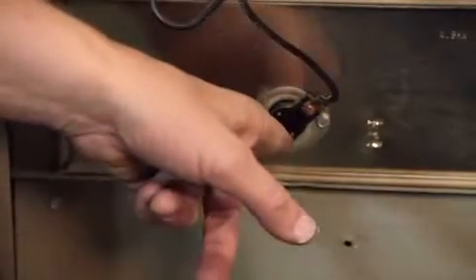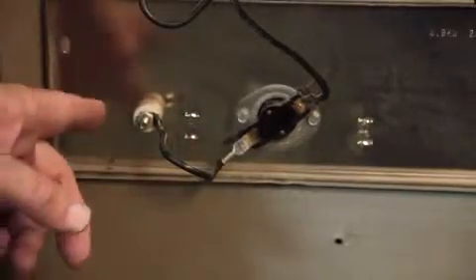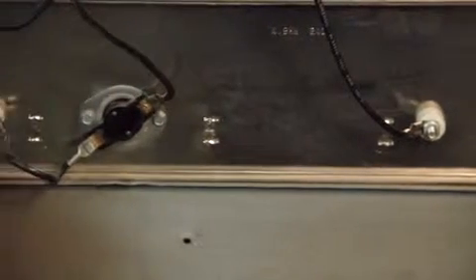We'll also check our overload devices. If we're checking this with the power on, we'll check for voltage to the heater. Then with an amp clamp, is it pulling amperage? If I have voltage to it and it's not pulling amperage, then the heater is no good.